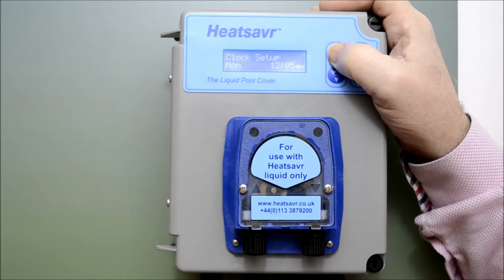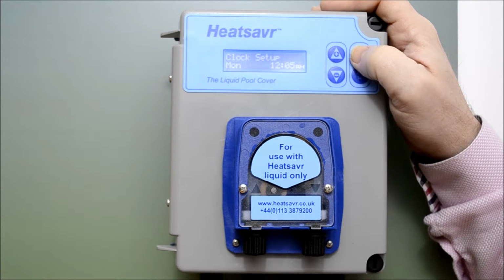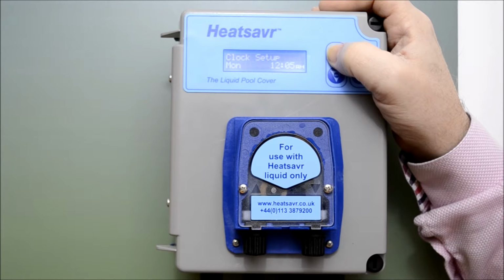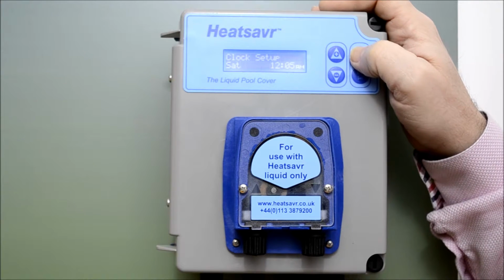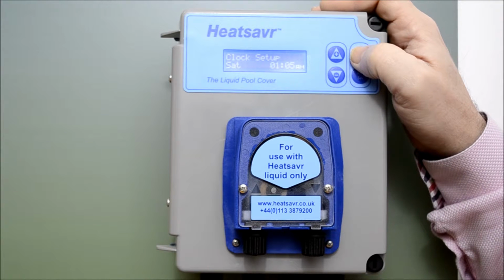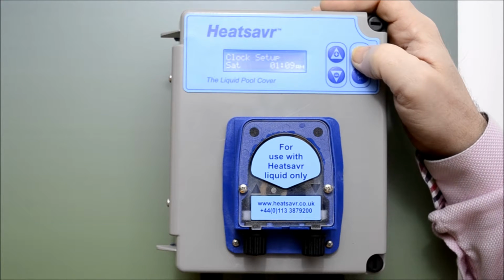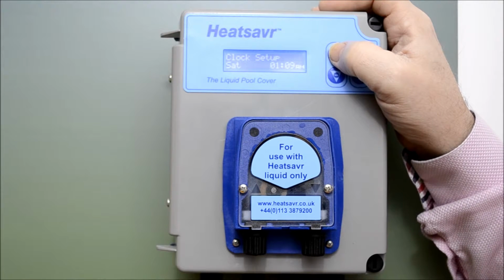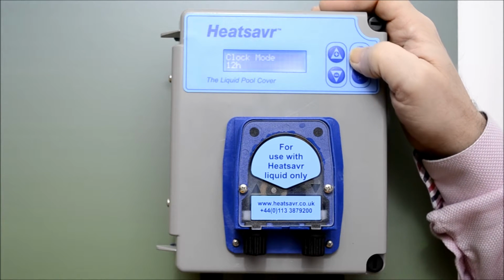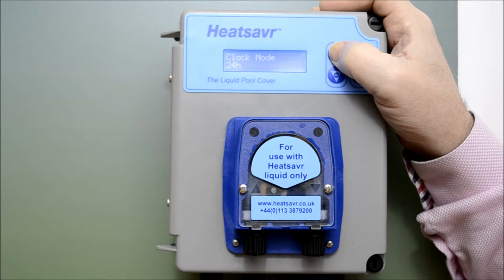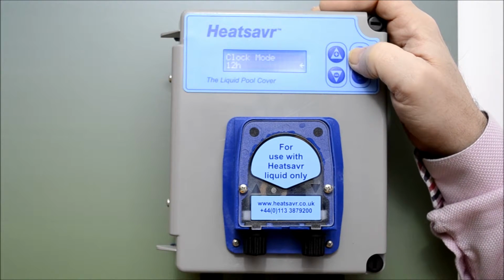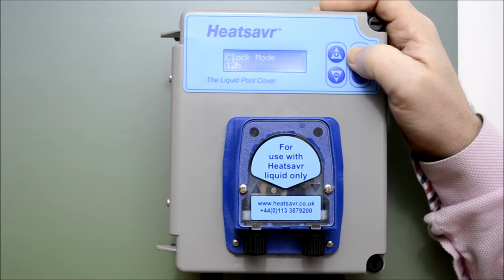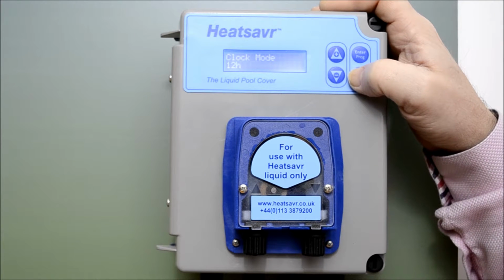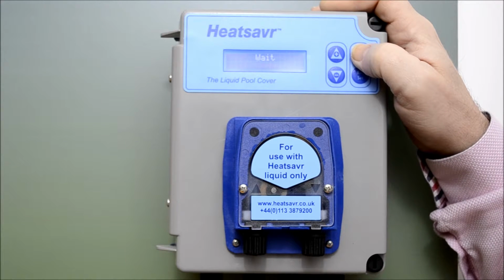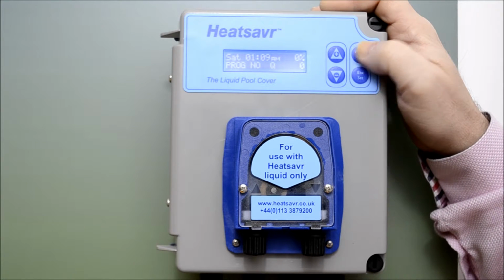Using the up arrow once more takes you to the clock set screen. Press enter and select the current day, enter to confirm, and move to the current hour and then the minute. The last stage of the clock setup gives you the option of a 12 or 24-hour clock. The 12-hour clock will show 1 to 12 followed by an AM or PM signal. Once this is selected, press the escape button and then enter to save the settings. The unit is now ready to be programmed.